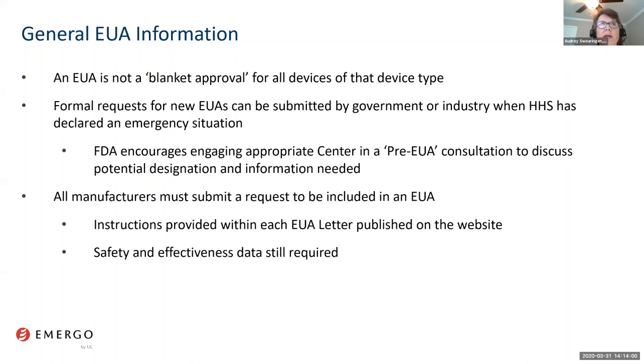First of all, on this slide, I want to point out that formal requests for new emergency use authorizations may be submitted by a government entity as well as industry whenever the emergency situation has been declared. If we're not currently in an emergency situation, but a company wants to prepare for a potential emergency use situation, then the FDA strongly encourages engaging the appropriate center in a pre-EUA discussion to consult with them on what would be needed. I also want to point out that an emergency use authorization is not a blanket approval for all devices of that device type.